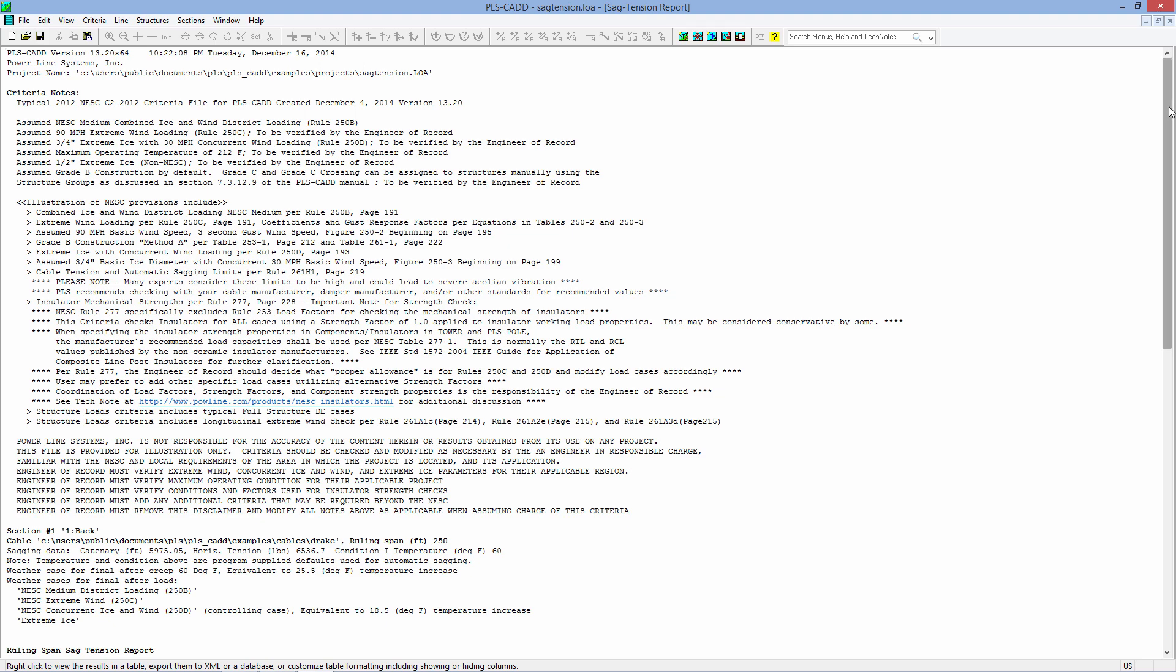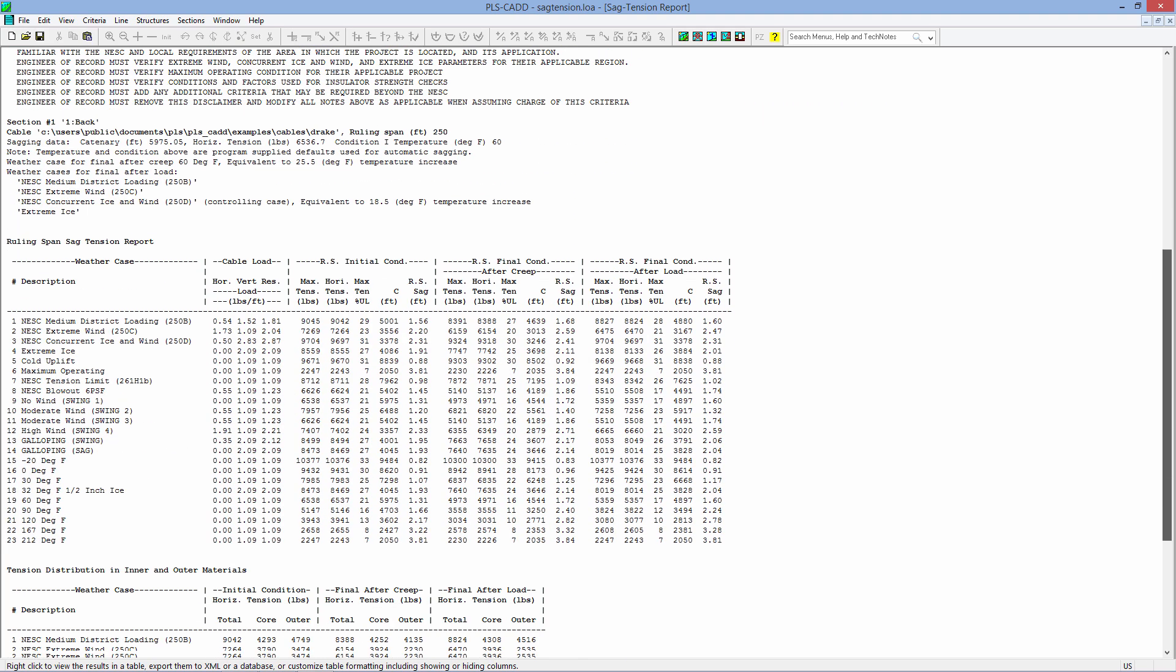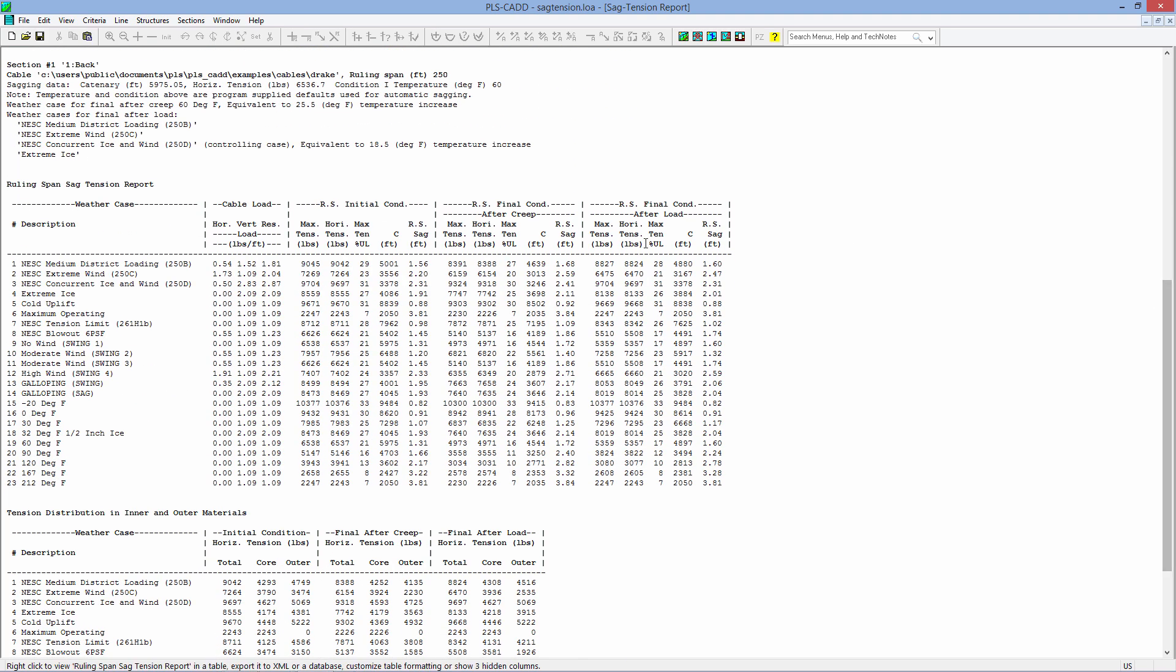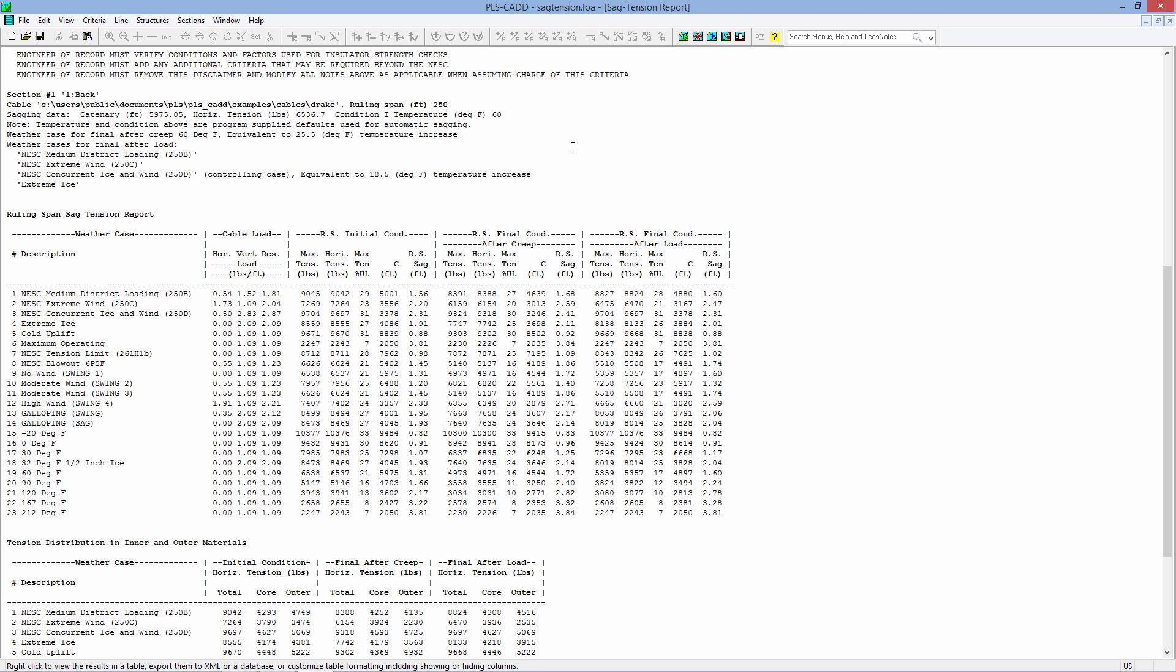I'll maximize this so we can see this in detail, and there is a sag tension chart. The default is a simple Drake ACSR 795 cable, and the default is a ruling span of 250 feet.